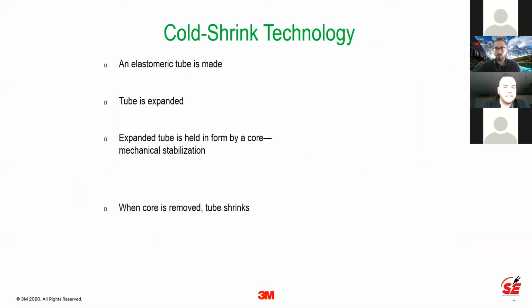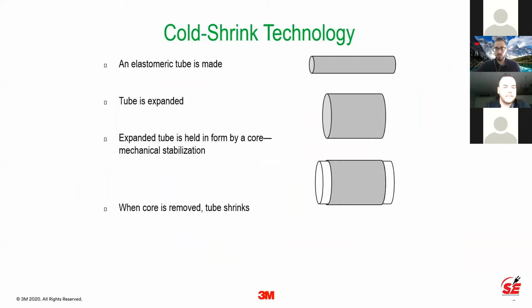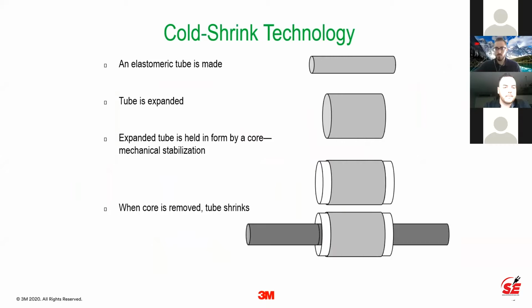Getting into the cold shrink technology: once the tube is made, it is then expanded. The expanded tube is held in form by a core, which is installed. When the core is removed, the tube shrinks, and there you have your cold shrink tubing with a living seal that is continuously pressing inward on the cable, even after the core is removed.